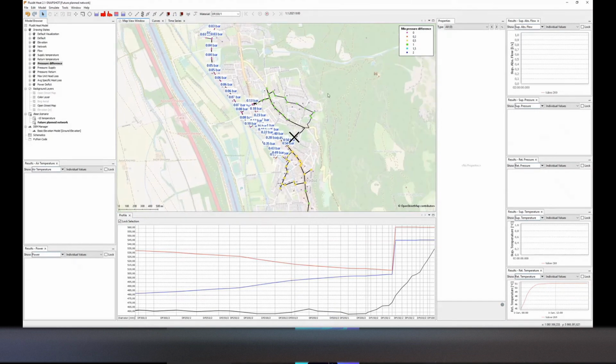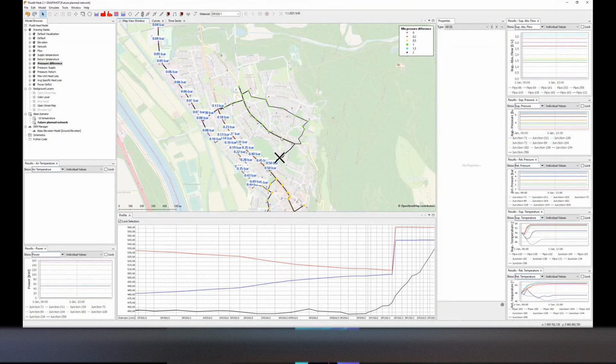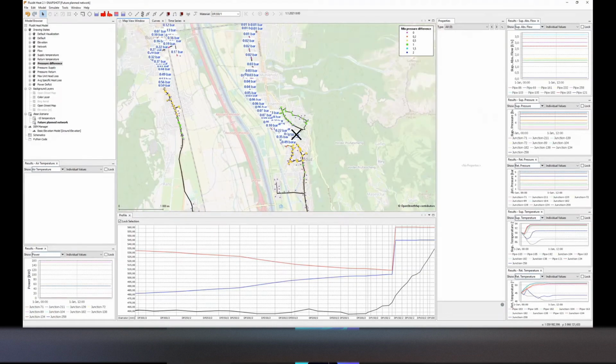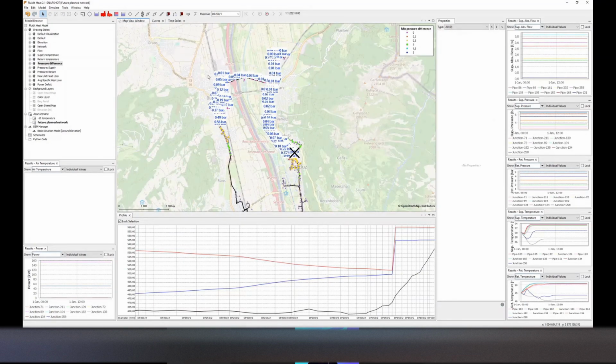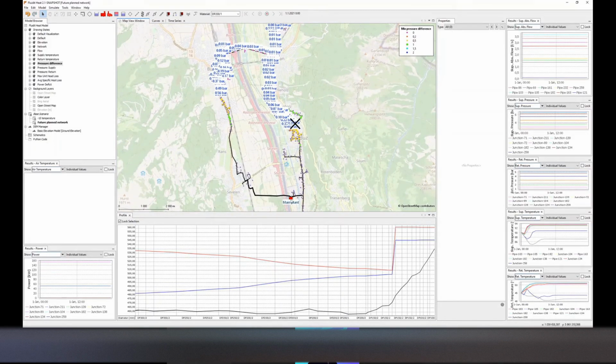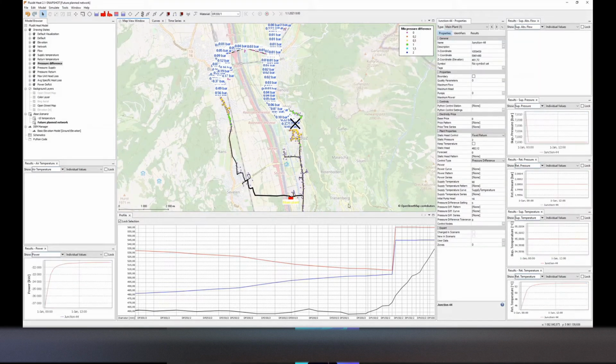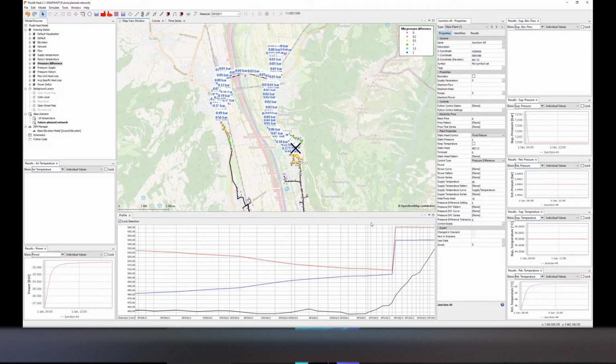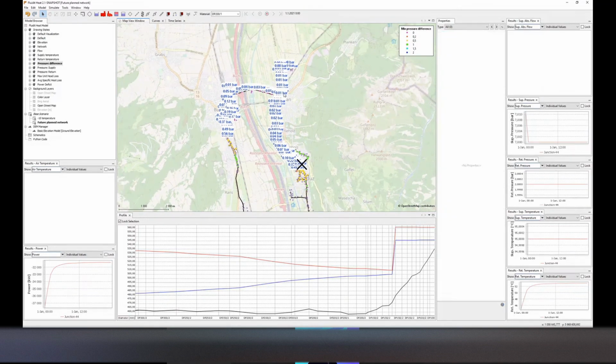So now we have fixed some issues that are here, but some issues are still really here in the north side that we can see. We could of course always increase the pressure difference setting of our main plant, but that might not be ideal to constantly always just be increasing.